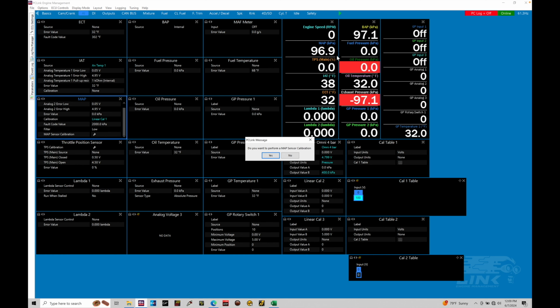This uses the scaling you've placed in the software, but makes an internal check between these two values, and automatically adjusts the offset difference between them. So we don't need to go in and adjust our scaling so they're identical, it does that process for us already.